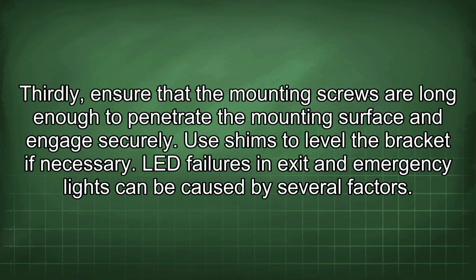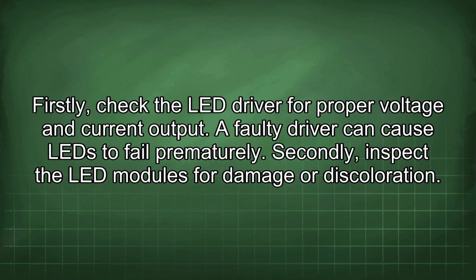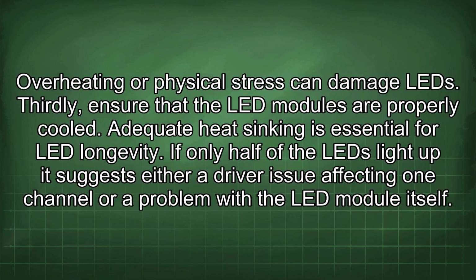LED failures in exit and emergency lights can be caused by several factors. Firstly, check the LED driver for proper voltage and current output. A faulty driver can cause LED to fail prematurely. Secondly, inspect the LED modules for damage or discoloration. Overheating or physical stress can damage LED. Thirdly, ensure that the LED modules are properly cooled. Adequate heat sinking is essential for LED longevity.